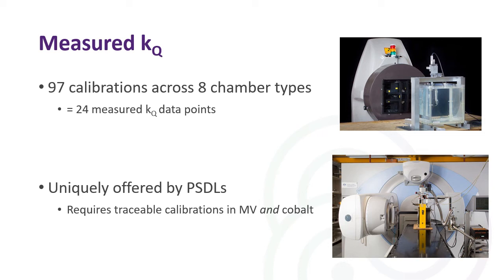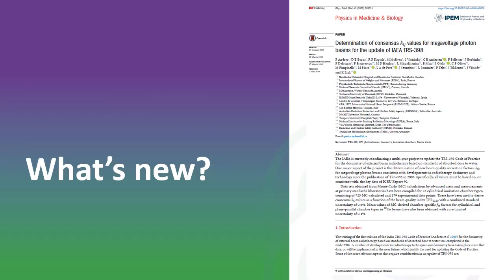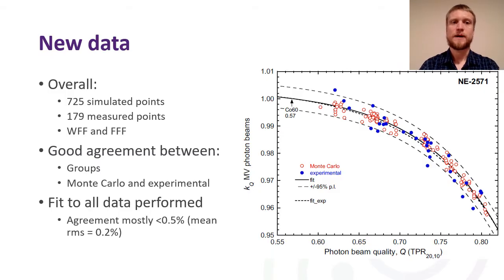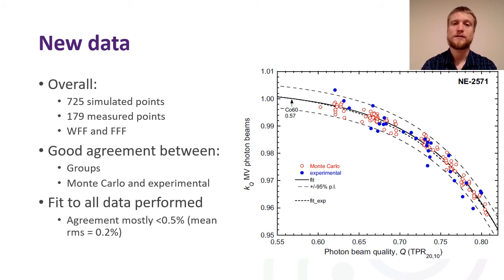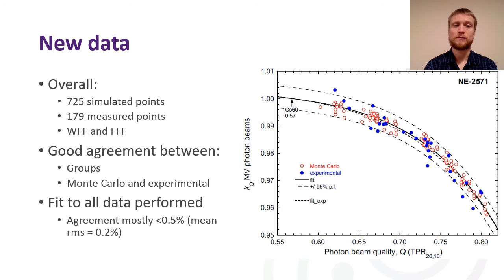The consensus data combines 725 simulated KQ data points and 179 measured KQ data points, including both flattening filter and flattening filter-free beam qualities. ARPANSA contributed 13% of the measured data points and 12% of the simulated data points. On the right hand side there's a representative figure for the NE2571 Thimble chamber, and you can see good agreement between most of the data points, demonstrating agreement between the different research groups and between the Monte Carlo and experimental data collected.